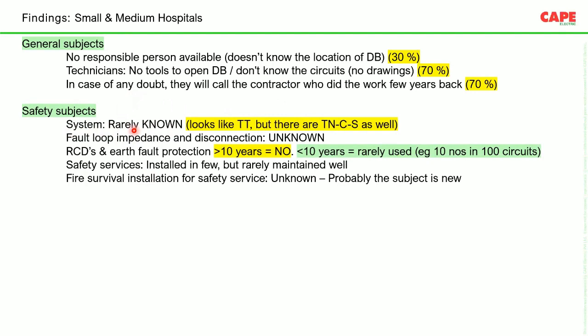With respect to safety, in smaller to medium hospitals, most of the safety requirements are unknown. It's very rarely known. The installation looks like a TT, but most often the system earthing, which is the most important for electrical safety, looks like TT but is a very, very inefficient way of, let's say, TNS or TNCS. And subjects like fault loop impedance are rarely known. In hospitals which are more than 10 years old, most have no RCD. In hospitals less than 10 years old, of course, in some cases RCDs are used. Probably 10%, 20% of the circuits have RCDs.